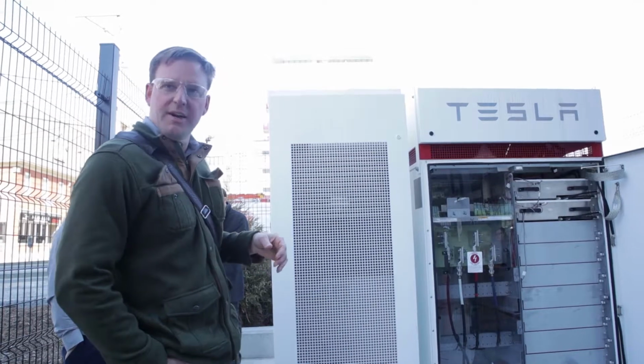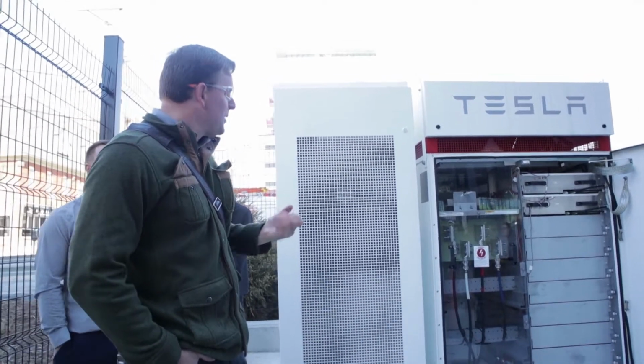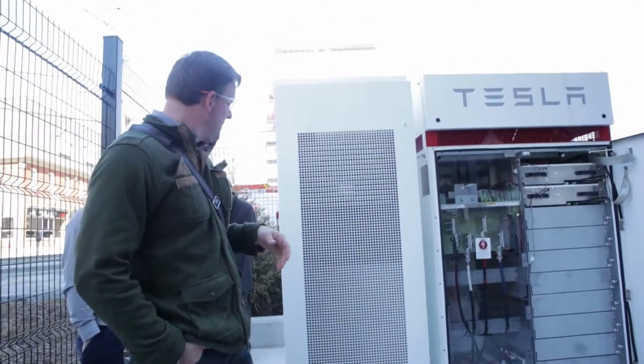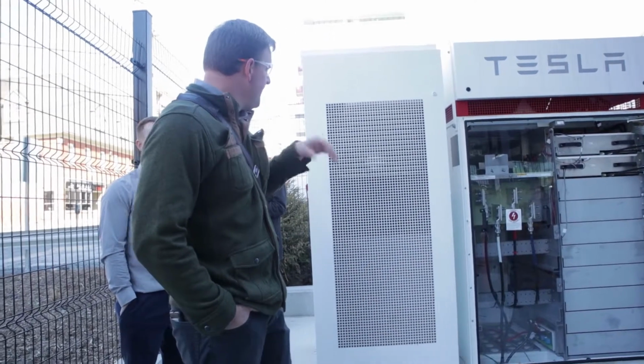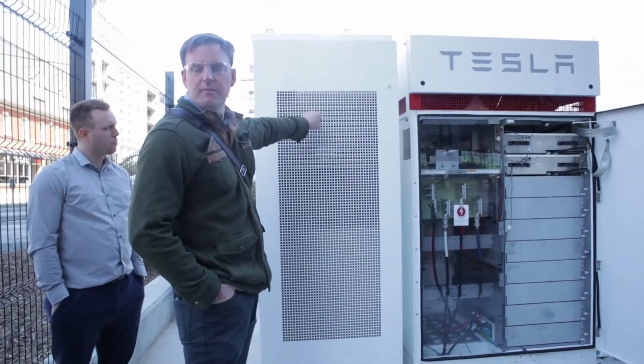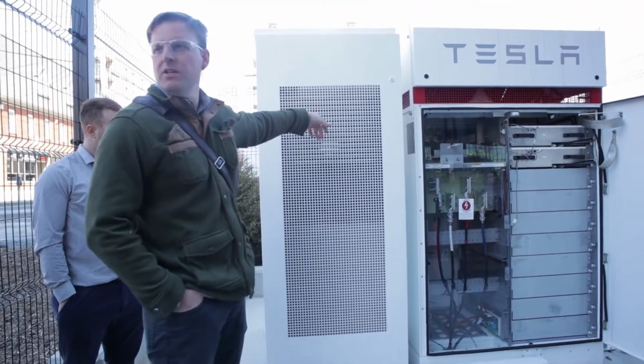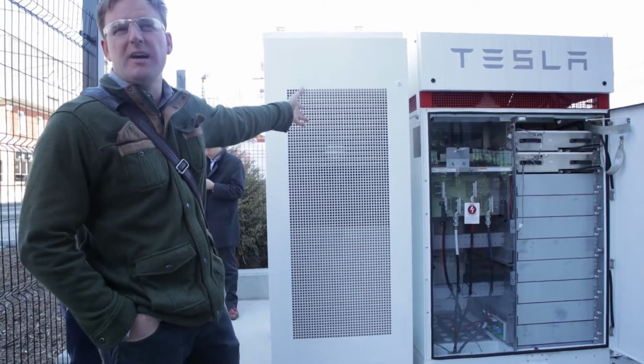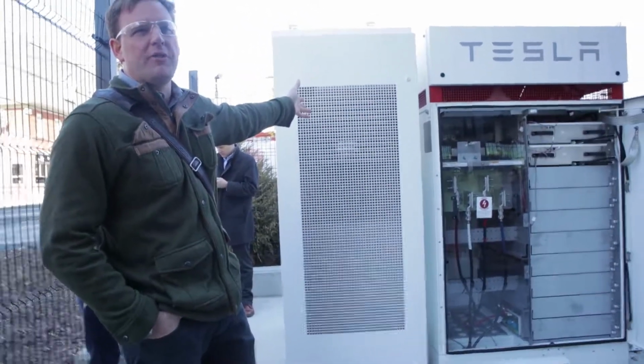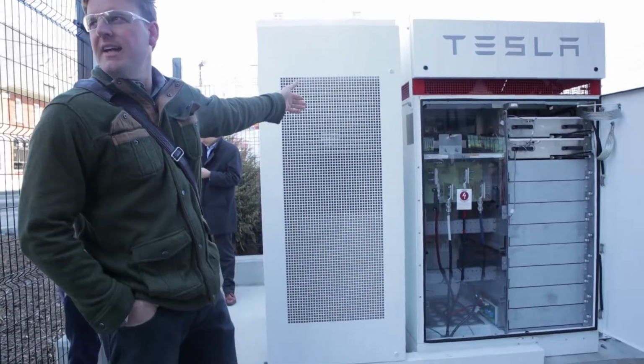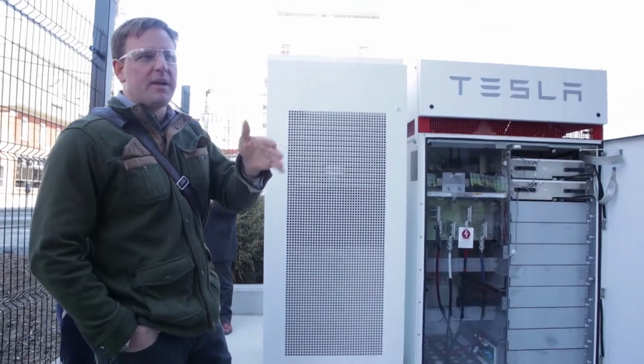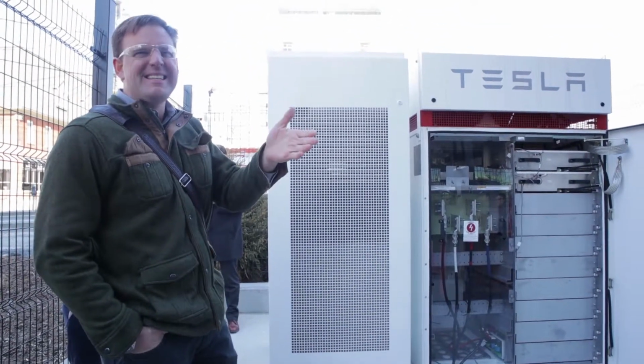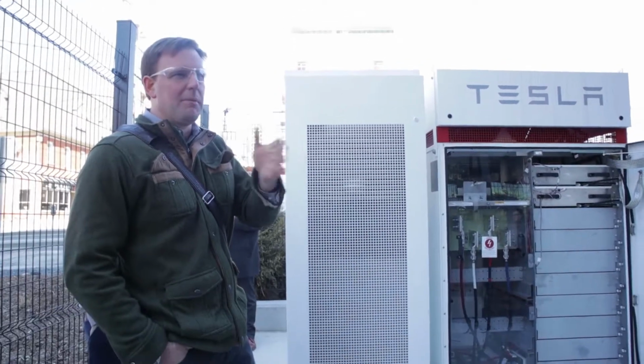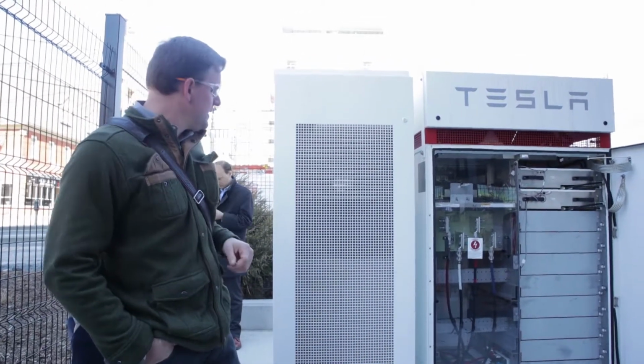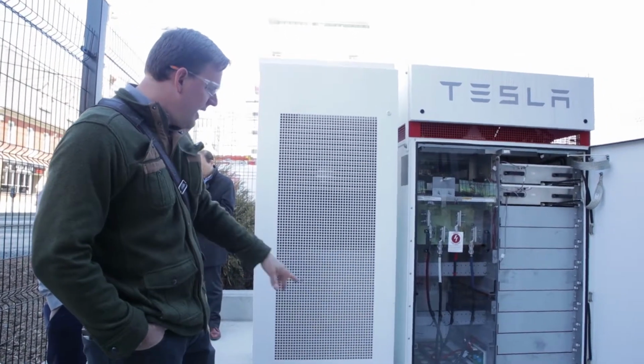Like today, it will be heating up somehow? Well, if you wanted to operate them hard today, you would absolutely be heating them up. And then there's usually a refrigerant-based cooling system right here on the front, so you could put these batteries in a very hot environment, say 40 to 45 degrees Celsius in the desert, and still keep them cool. Their nominal operating temperature range is about 10 to 40 degrees Celsius, though they'll go a little bit outside those realms in typical operation.